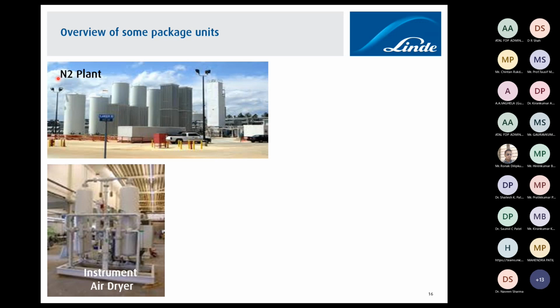Thank you, Dr. Jani. Yes, you rightly said. Typically in an industrial dryer, because you are operating at a certain pressure, you have two ways of measurement. Let's say this is my outlet line, or dry air outlet. How do we measure it? Either we can measure at a particular pressure, because this is operating at roughly around 7 bar, and then it becomes the pressure dew point. And if you have a sample point and you bleed the air into the atmosphere and measure at atmospheric level, then that is called the atmospheric dew point. As you know, there is a good relationship between atmospheric dew point and pressure dew point. Sometimes when customers specify, we need to ask back: do you mean pressure dew point or atmospheric dew point? Because typically -40 degree C is the expected dew point at atmospheric condition. This is by and large used in various industries.